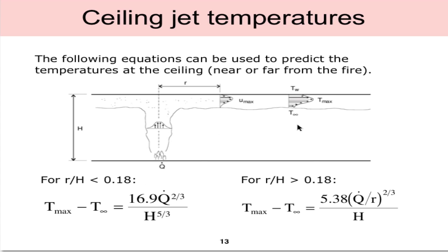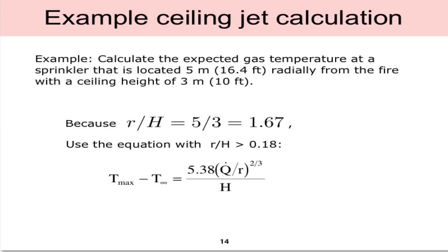There are equations from the textbook that can be used to predict the temperatures at the ceiling, either in the near field of the fire or some radial distance r from the fire. These two equations are given for different conditions. In this case, if the ratio of r over h is less than 0.18, we use this equation. In the case where r over h is greater than 0.18, we use this equation. Depending on if we're near or far from the fire, these different empirical equations apply.